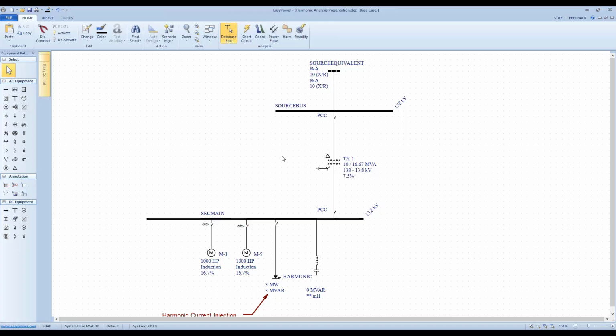One key thing I think I should mention, that if you are doing measurements and there are capacitor banks in the network like this here, if you're taking measurements here, for your measurements to have meaning, it is an absolute requirement that these capacitor banks be off. So remember, there can be harmonic amplification between the capacitor here and the network here. To take harmonic measurements with the capacitors online at this point would be to be inside that resonating circuit, and your measurements will not have meaning. They could be either high or low depending upon where you are in frequency. So harmonic measurements on a plant-wide basis should be taken while the capacitors are offline.